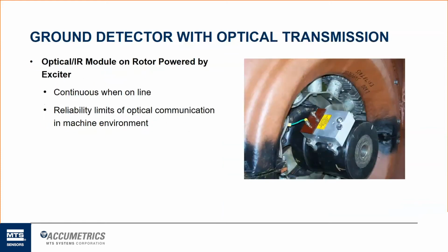So the next style of ground fault detector is an optical transmission. This is just an optical IR module that mounts out on the rotating shaft. It gets its power source from the excitation of the field voltage itself. So it is continuous as long as the machine is online and running. It does have some reliability limits, of course, for an optical communication in a machine environment. If it's in a coal plant, a dirty or dusty environment, those lenses can get corroded or covered up, and obviously it stops working if that happens.